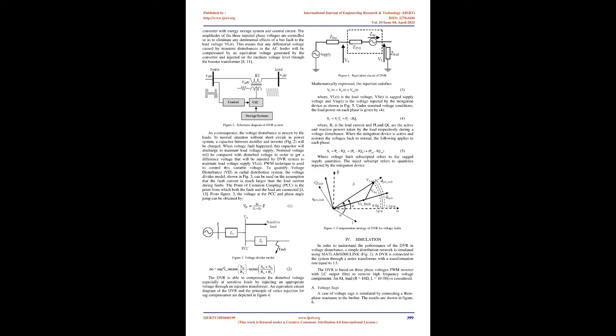The purpose is to supply the necessary energy to the VSC via a DC link for the generation of injected voltages. The different kinds of energy storage devices are superconductive magnetic energy storage, SMES, batteries, and capacitance. The capacity of the stored energy directly determines the duration of the voltage disturbance which can be mitigated by the DVR. DC charging circuit. The DC charging circuit has 2 main tasks.